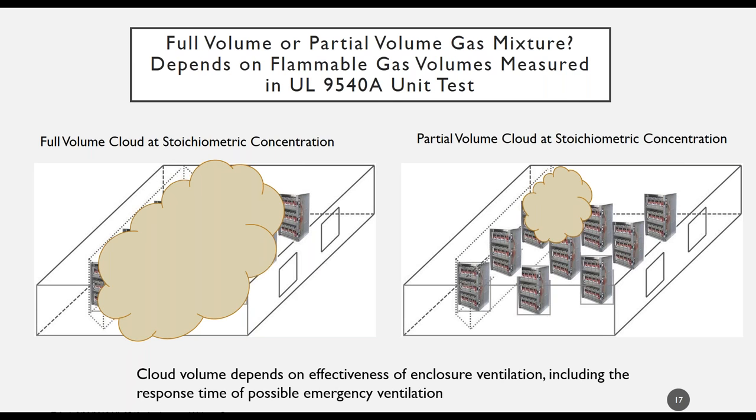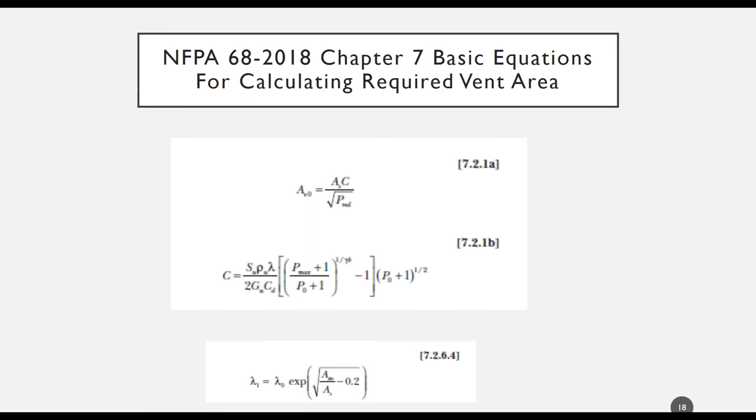The cloud volume depends, I should point out, on the effectiveness of enclosure ventilation. That's a very important aspect that we probably should spend more time on next week, including the possible response time of emergency ventilation that's actuated in response to detection of the runaway or of flammable gas being generated. Next, please.